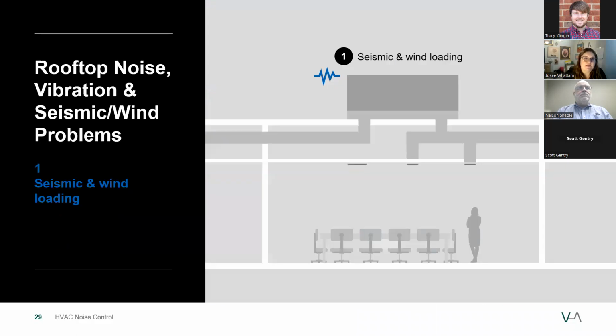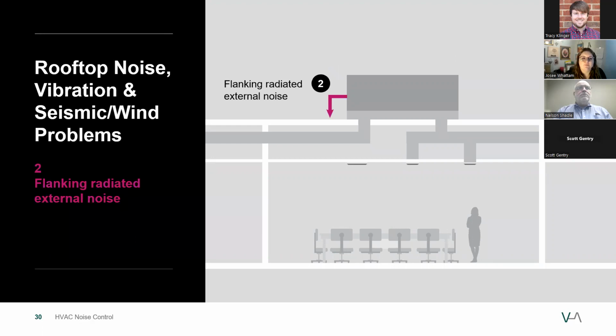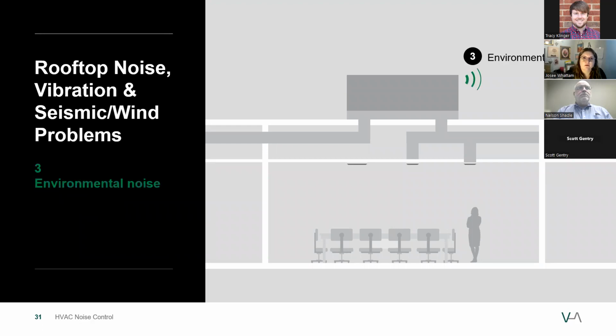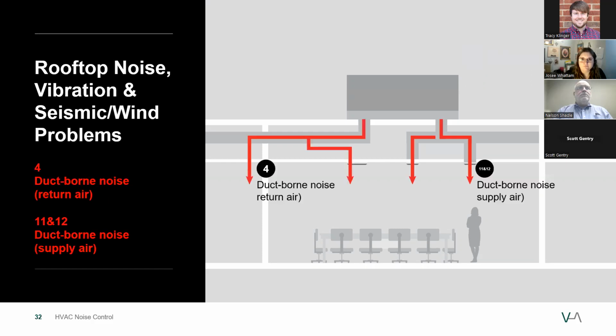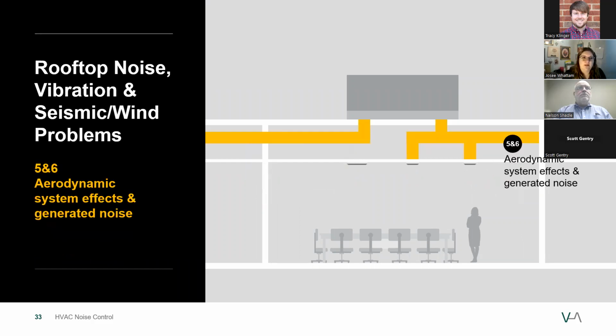So first is the seismic and wind loading. So any movement caused by either of these events could produce some noise. Next, there's flanking radiated external noise. So that's noise produced by equipment transferred through the roofing material from the exterior. Next is environmental noise. So rooftop equipment and outside air intake and exhaust from mechanical rooms have the potential to exceed community noise bylaws at property lines. Next is ductborne noise. So that's noise transported by the air being supplied or returned to the spaces. Next is aerodynamic system effects and generated noise. The air itself would be producing noise while moving along the entire system.